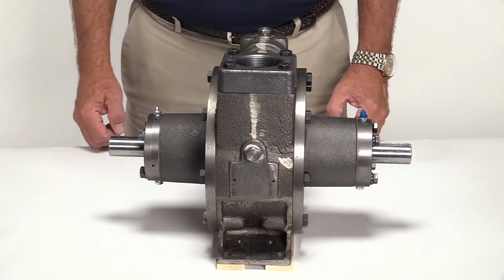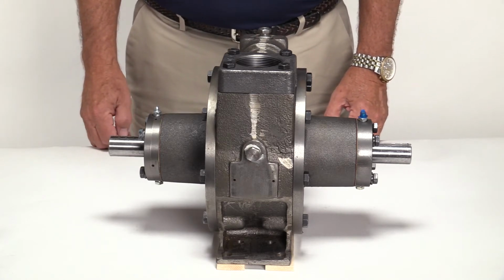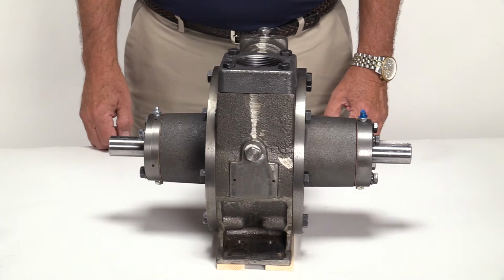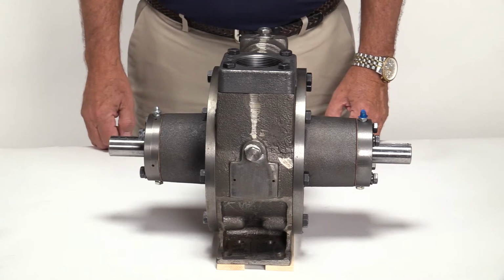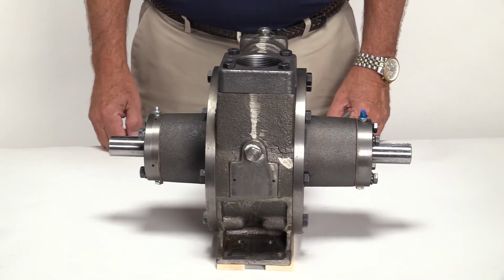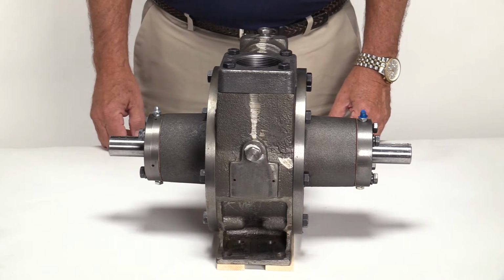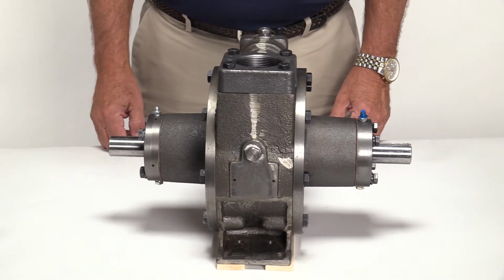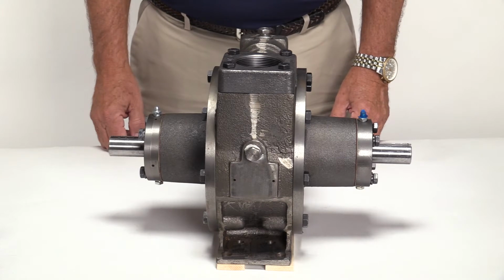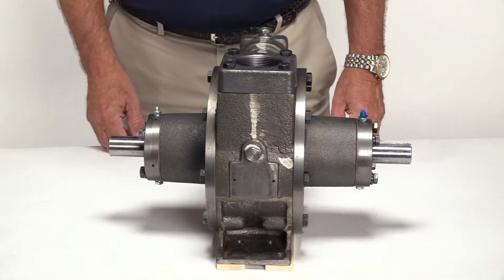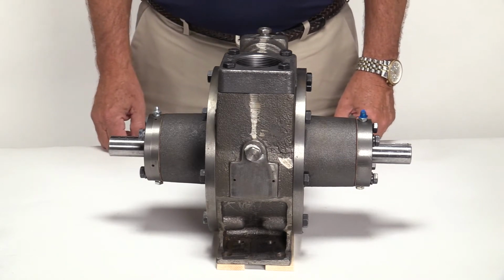Typically, the only time a Corken sliding vane pump is shimmed is before it leaves the factory, after installing major components, or installing a full rebuild kit. Since rebuild kits include a rotor shaft assembly, cam, side plates, and cover, the stacking order of these parts may differ from the original parts, causing the rotor to rub against one of the side plates.